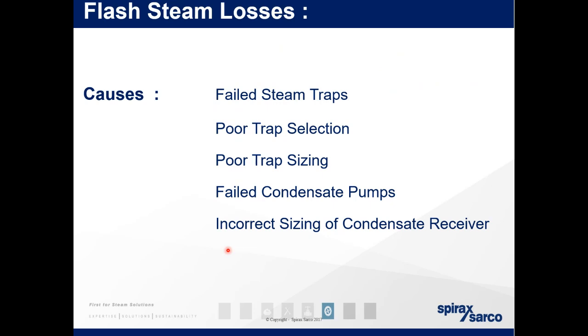So fouling, stalling, yeah. Effectively, anything that increases the back pressure in a system. If you've got a condensate pipe that's sized for a certain load, and you have scaling or any kind of buildup or residue on that pipe, you're reducing the bore. Therefore, the back pressure is going to increase. That will then cause an issue with stall, or can cause an issue with stall.